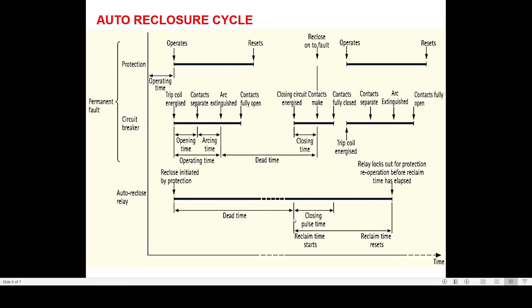If within the reclaim time — which is 25 seconds — there is a second fault, your protection relay sees the second fault, operates, and energizes the tripping coil. Since the reclaim time is in process, the autoreclosure relay will issue a three-pole tripping command and the breaker will be in the lockout condition. This is the complete AR cycle. The dead time of the autoreclosure relay must be higher than the dead time of the circuit breaker for successful autoreclosure.